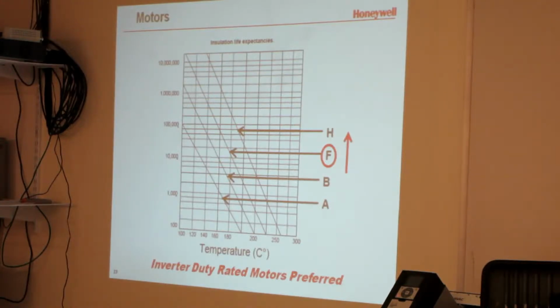If you're going to put a drive on a motor, you want to make sure it's inverter rated. One that's designed to take a drive. There are motors out there that are not designed to take a drive. And some of you experienced that. I have.